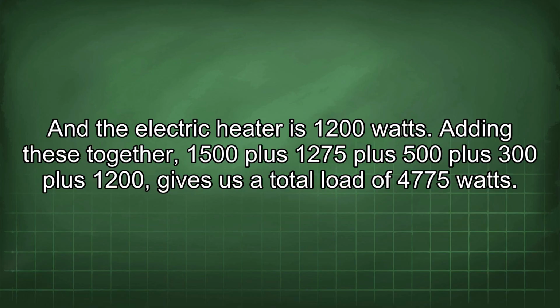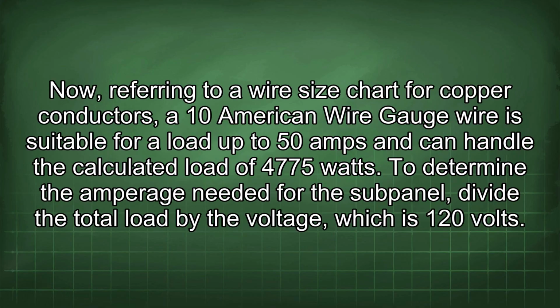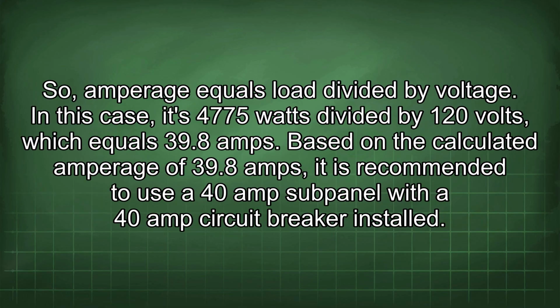4775 watts. Now, referring to a wire size chart for copper conductors, a 10 American wire gauge wire is suitable for a load up to 50 amps and can handle the calculated load of 4775 watts. To determine the amperage needed for the subpanel, divide the total load by the voltage, which is 120 volts. So amperage equals load divided by voltage. In this case, it's 4775 watts divided by 120 volts, which equals 39.8 amps.